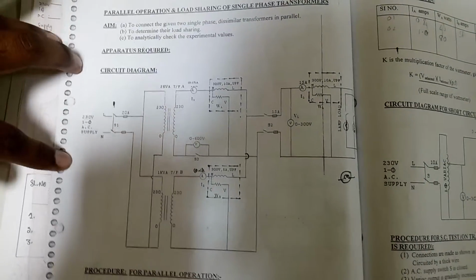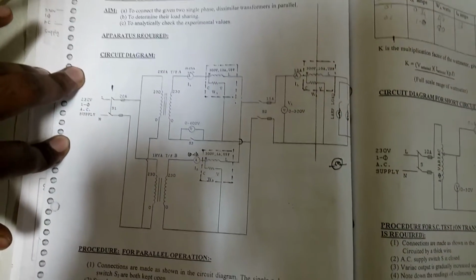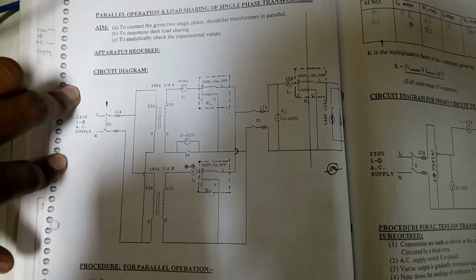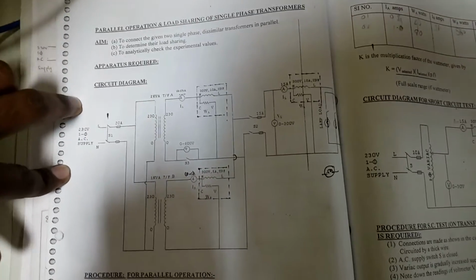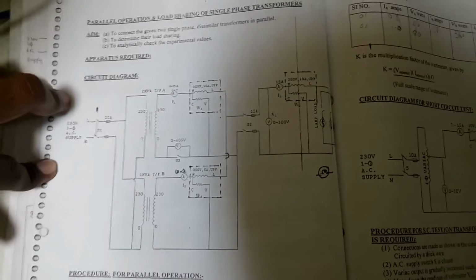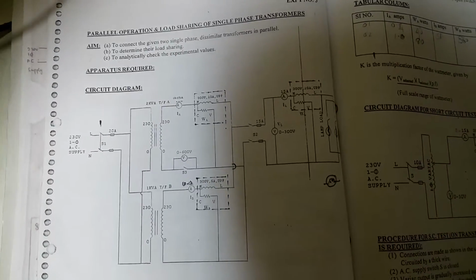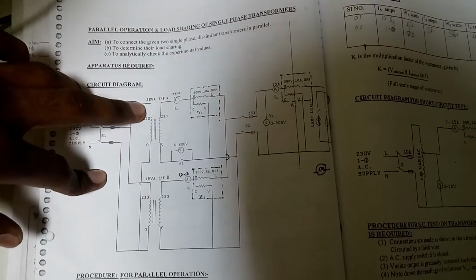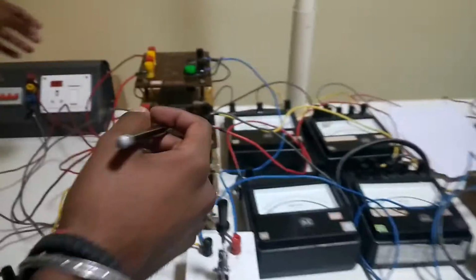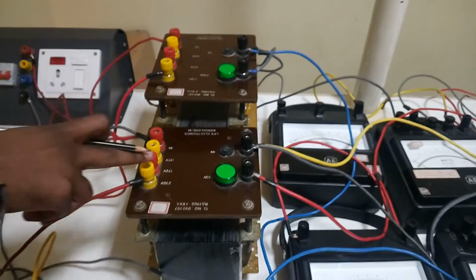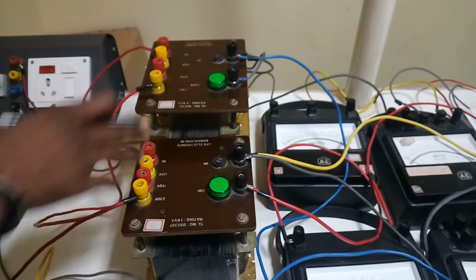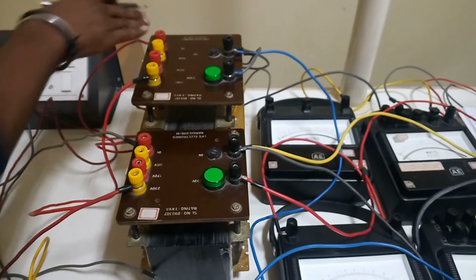So this is the circuit diagram for parallel operation of two transformers. Keep in mind that these two transformers are dissimilar transformers, and the positioning of the transformer is the basic thing. First, you need to keep the 2 kVA transformer. Second will be the 1 kVA transformer. Come to the points. Here, 230 and 230 of the 2 kVA and 1 kVA transformers are shorted, 0 and 0 are shorted.